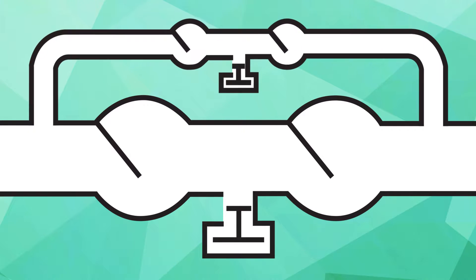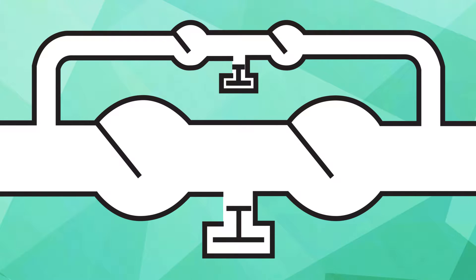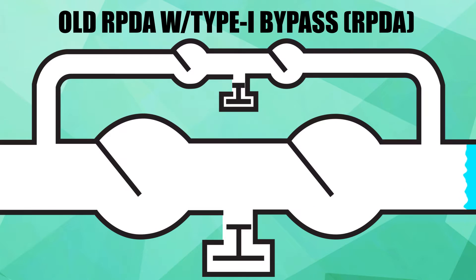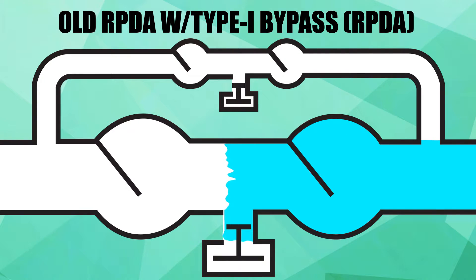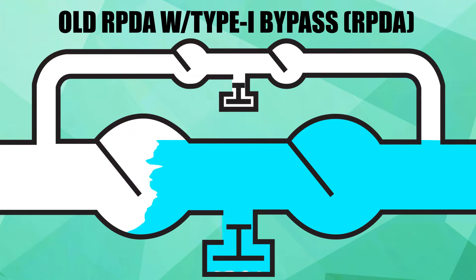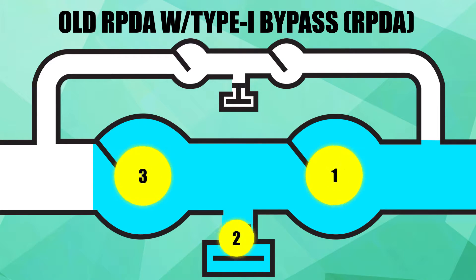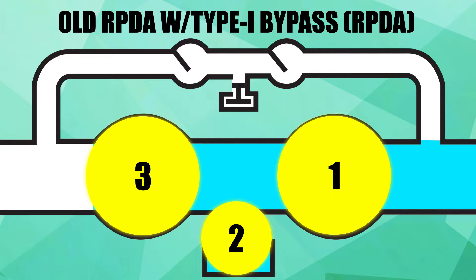First, a comparison of the paths through the main valve. During a backflow condition on an old RPDA with a Type 1 bypass, the water first encounters the main valve second check. Next, the water encounters the main valve relief valve. And then the water encounters the main valve first check. This provides three mechanisms of backflow protection.